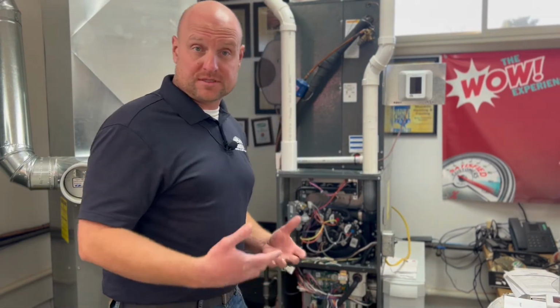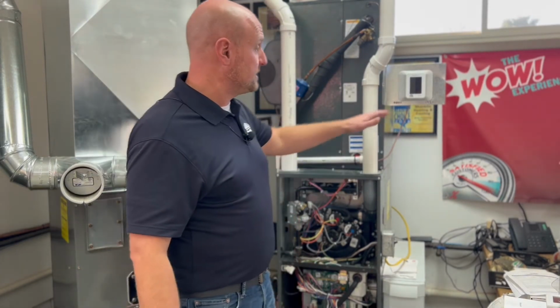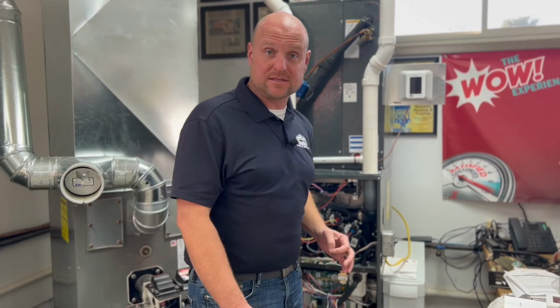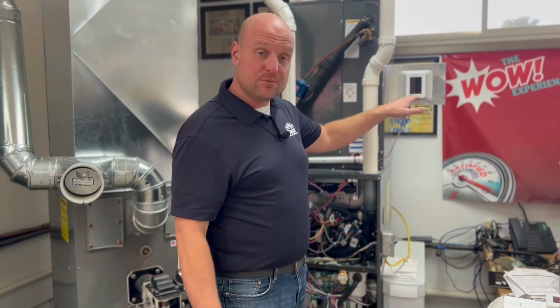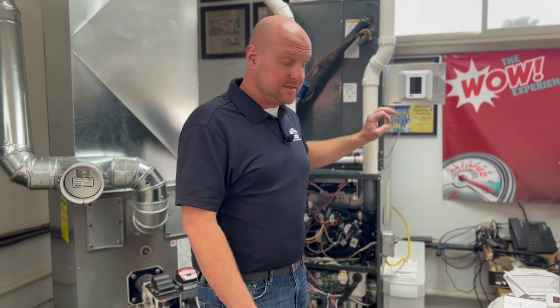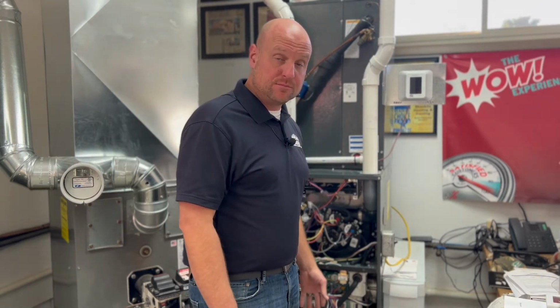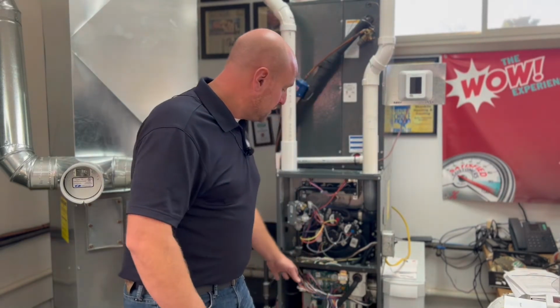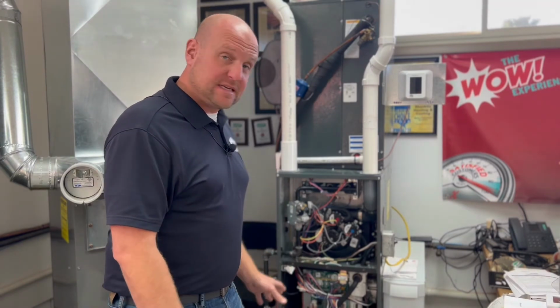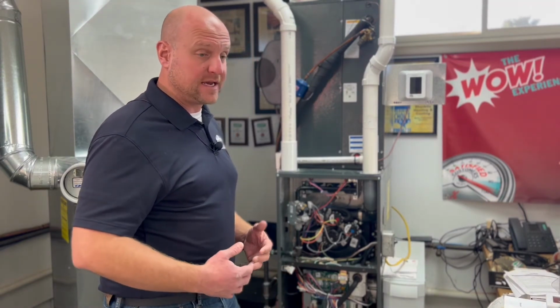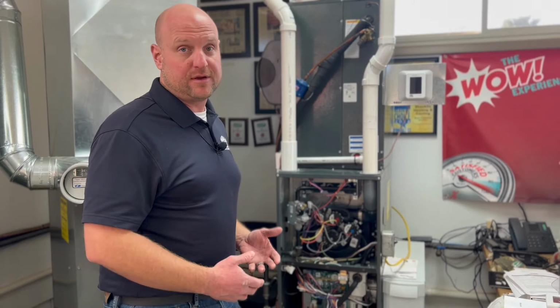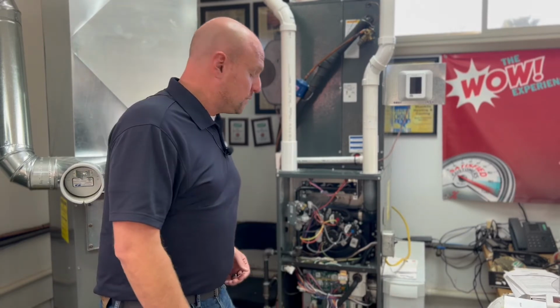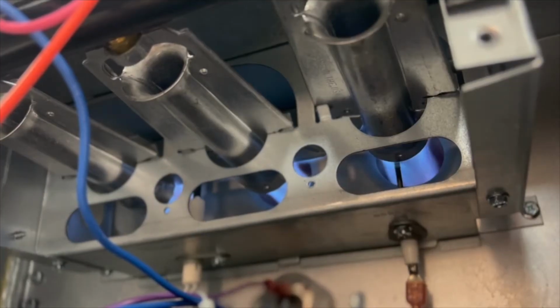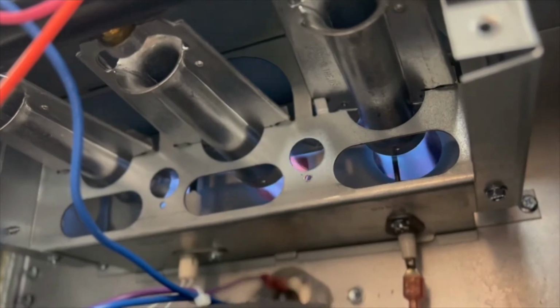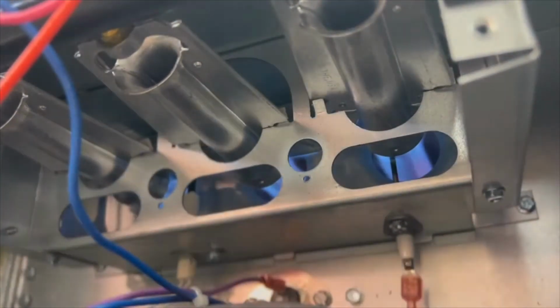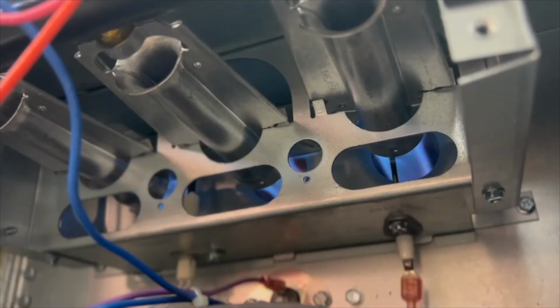After the space heats up to the desired temperature that the thermostat is set to, the thermostat then removes the call we first had, removing that 24-volt call to the W terminal. This tells the circuit board and furnace that, okay, I should be done heating now. It's going to start shutting down. The very first thing it does is remove the 24 volts from the gas valve. It will cause it to close, causing the flames to immediately turn off.